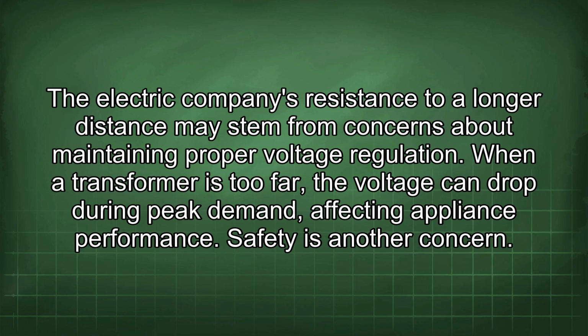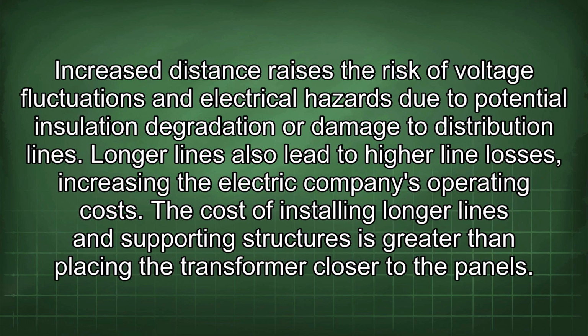When a transformer is too far, the voltage can drop during peak demand, affecting appliance performance. Safety is another concern. Increased distance raises the risk of voltage fluctuations and electrical hazards due to potential insulation degradation or damage to distribution lines. Longer lines also lead to higher line losses, increasing the electric company's operating costs. The cost of installing longer lines and supporting structures is greater than placing the transformer closer to the panels.